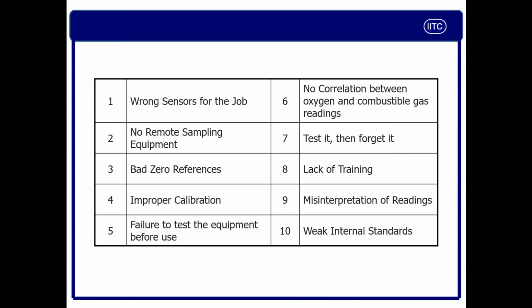So guys, these are the 10 major mistakes we make in confined space testing. First is wrong sensor for wrong job. Second point is no remote sampling equipment. Point number 3, bad zero reference. Point number 4, improper calibration. If you don't calibrate your instrument, probably you will get a wrong reading. Number 5, failure to test the equipment before use.